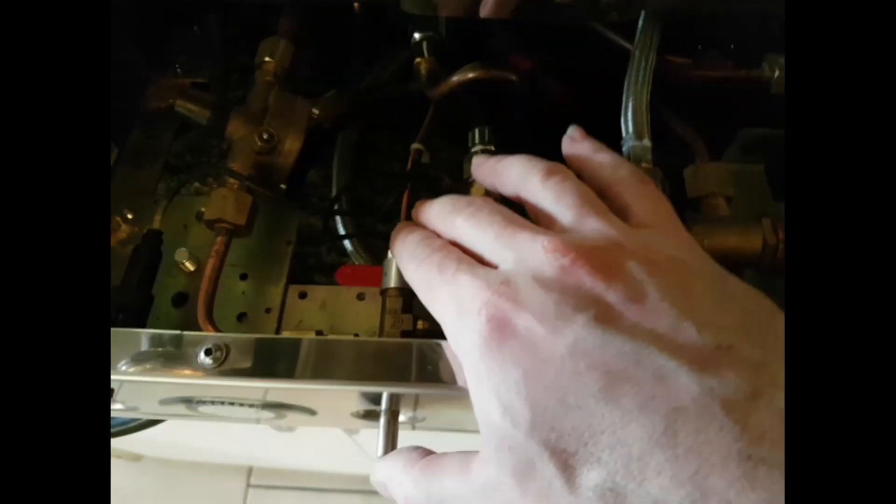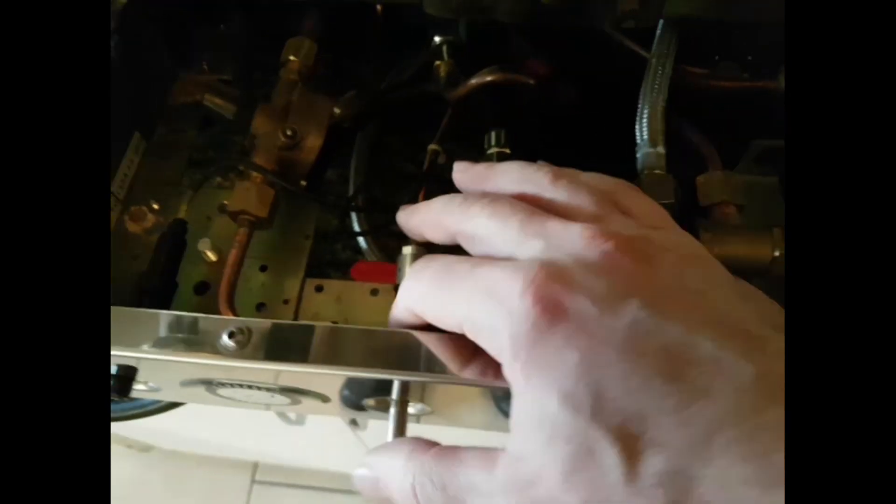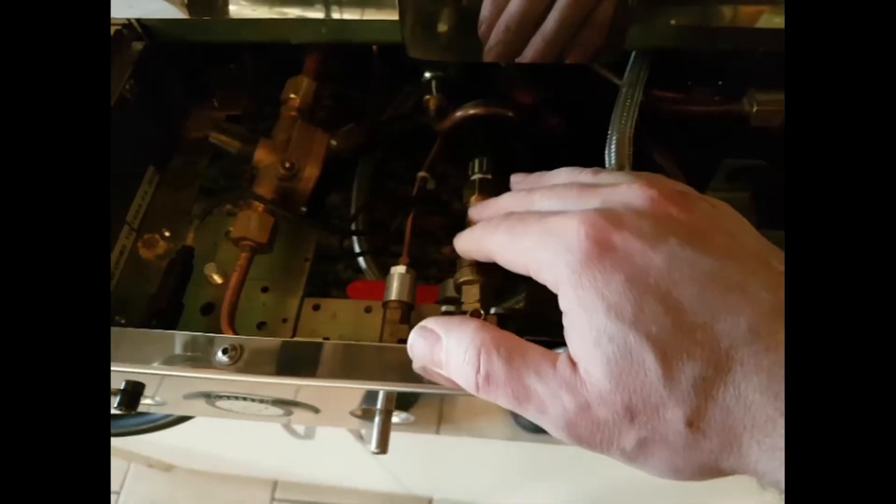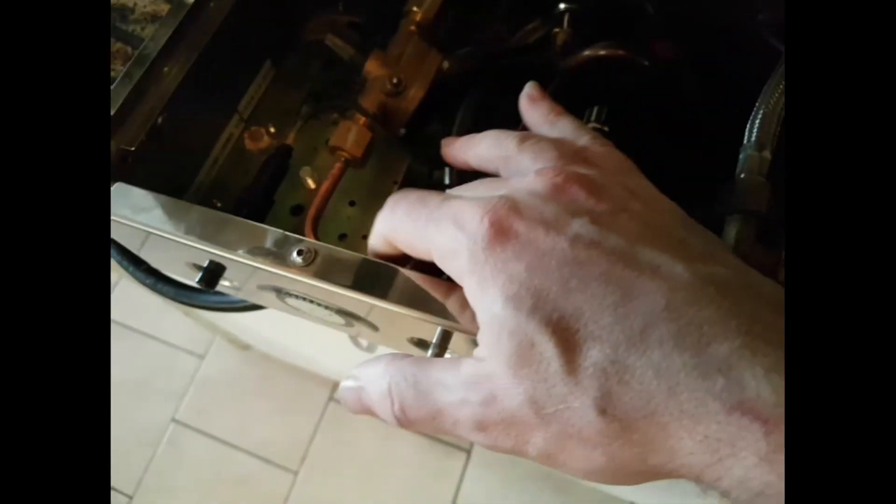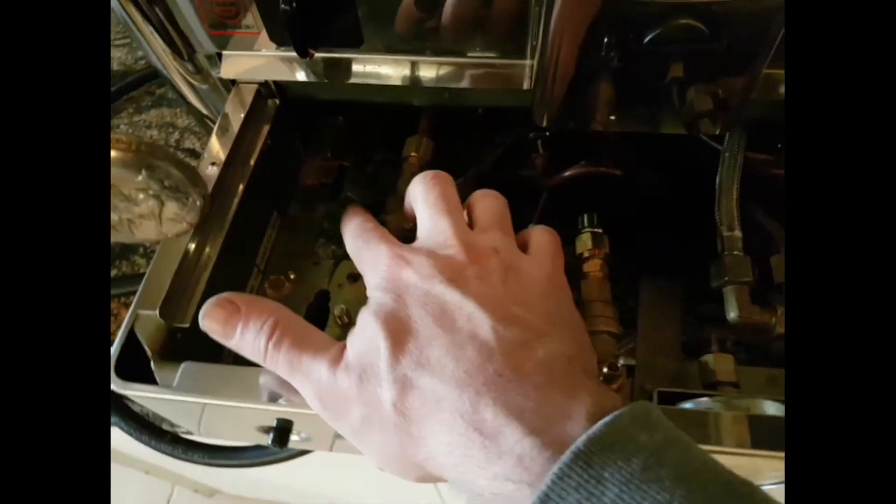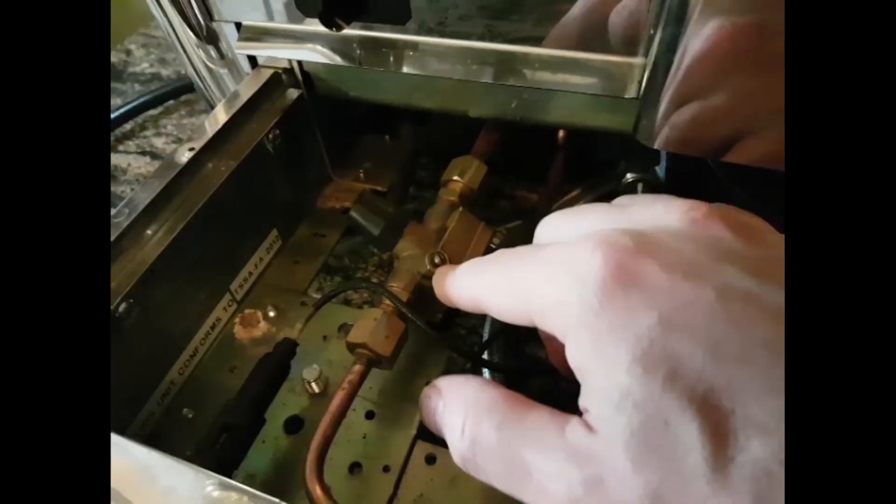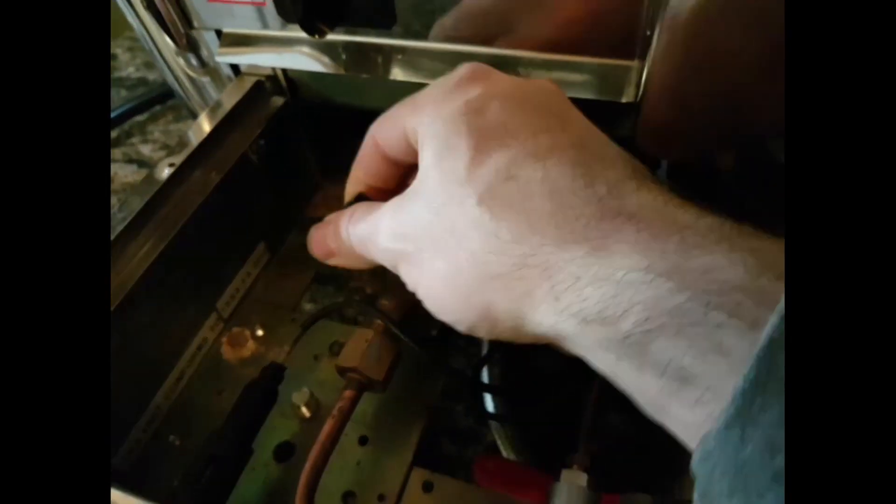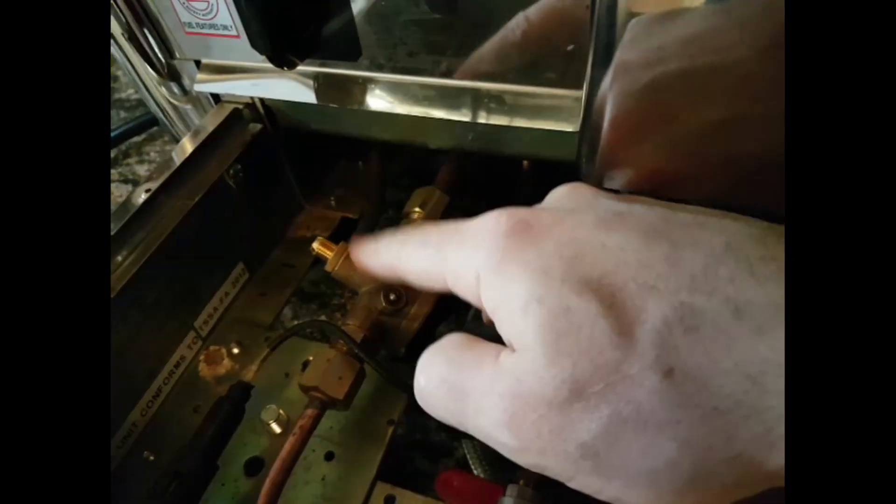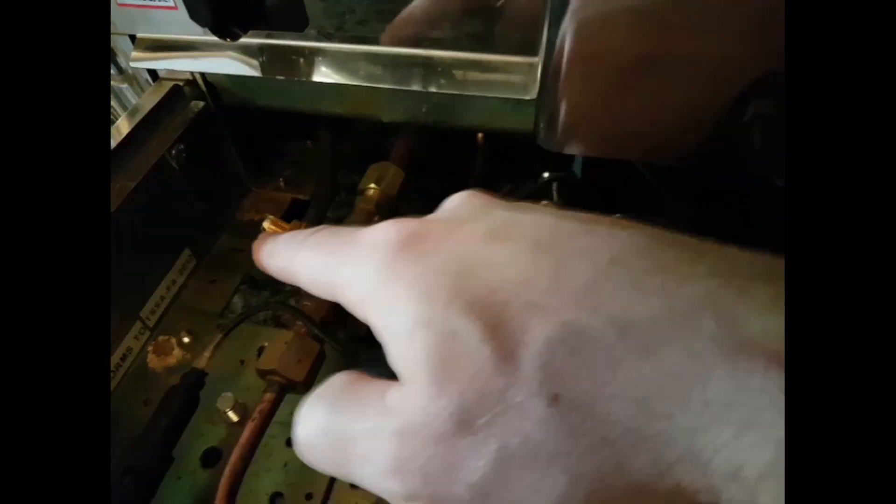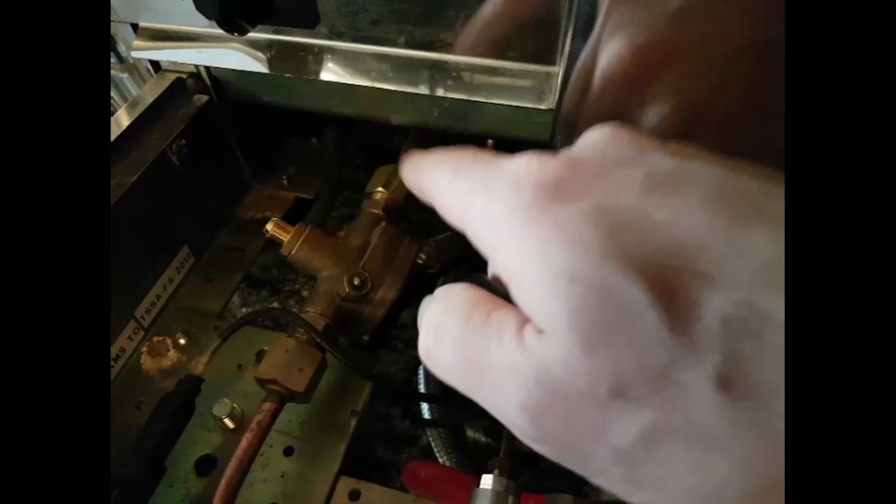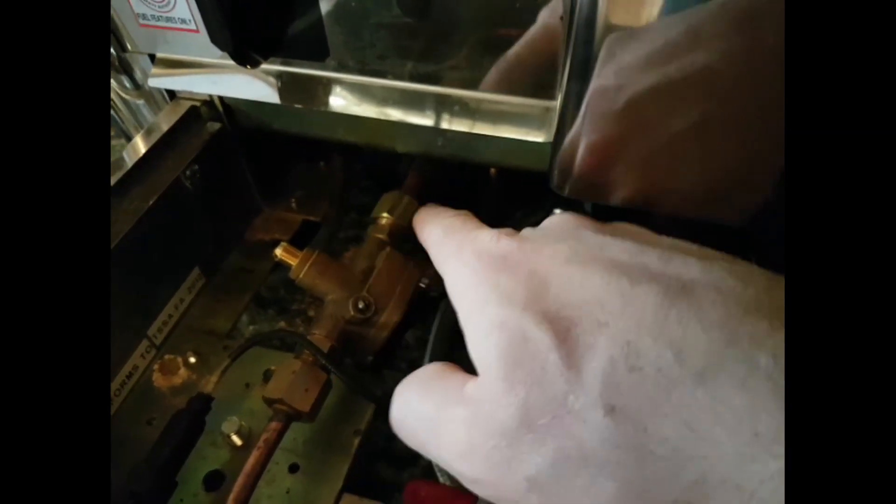And then from there it goes to what's called a safety shutoff. This is a device that is designed to shut off the flow of fuel to your regulator in the event that the flame is snuffed out. From the safety shutoff, it goes to your regulator and there's two adjustments here. This is basically your idle flame size. And then this will adjust your equilibrium point at which the steam pressure will throttle the regulator back and cut the flame down to idle.